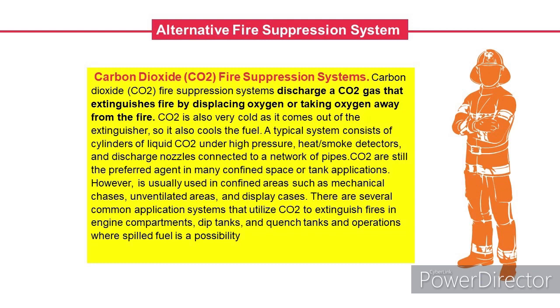CO2 is also very cold as it comes out of the extinguisher, so it also cools the fuel. A typical system consists of cylinders of liquid CO2 under high pressure, heat/smoke detectors, and discharge nozzles connected to a network of pipes. CO2 is still the preferred agent in many confined space or tank applications. However, it is usually used in confined areas such as mechanical chases, unventilated areas, and display cases.